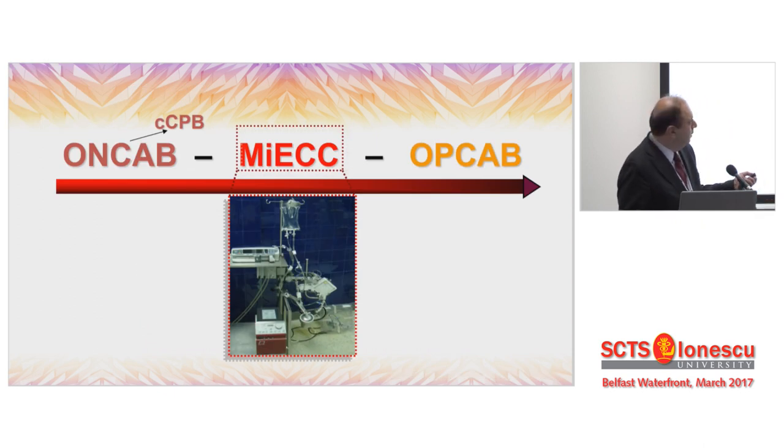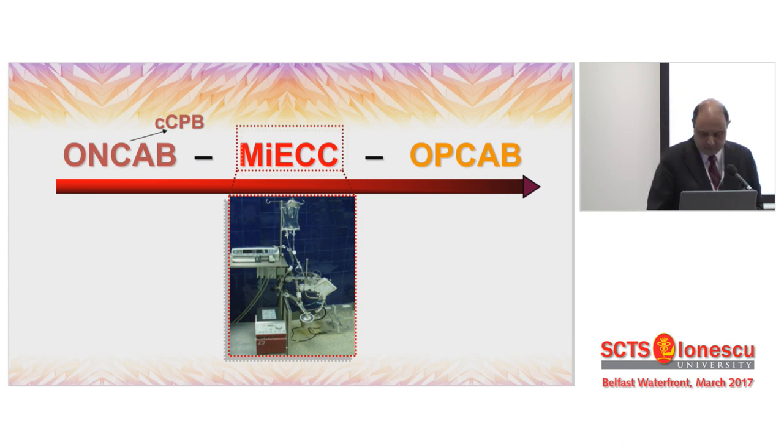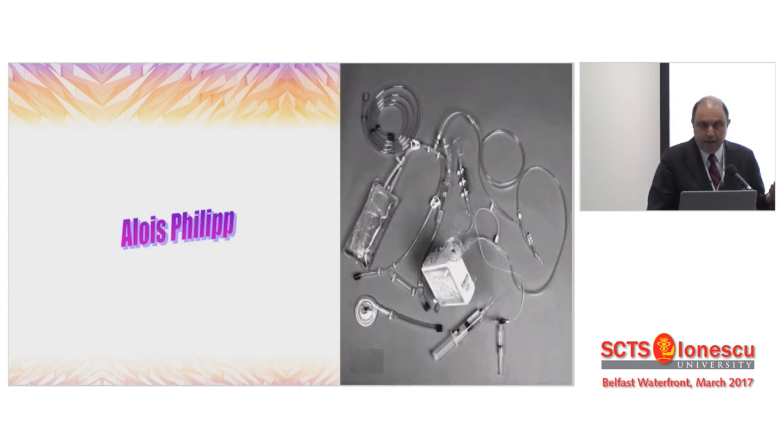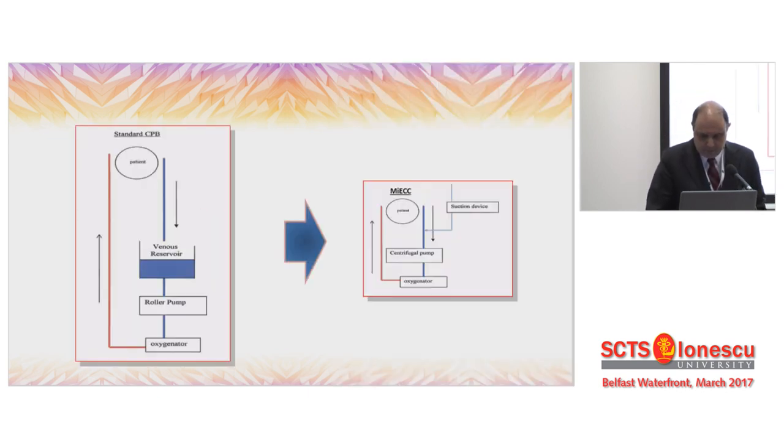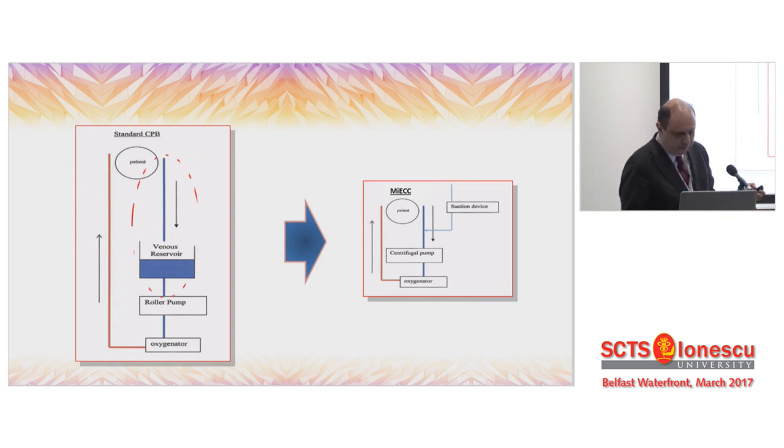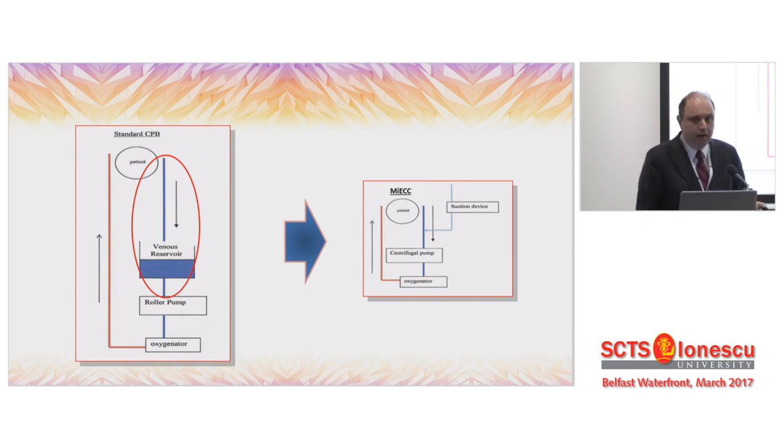With this background, it seemed there was a space initially some 10 to 15 years ago for the minimal invasive extracorporeal circulation. Everything started from this system, which is literally an ECLS system — an ECMO system mounted with a cardioplegia set. The key difference between these two designs is that there is an absent venous reservoir in the mini-system, creating a closed system with no blood-air interaction. Also, we do not have shed blood coming from the mediastinum into the system.